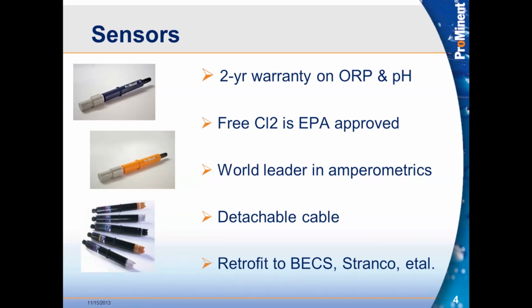Our free chlorine sensor is EPA approved, and it's the only chlorine sensor that has this approval rating to be used in drinking water applications without a backup wet test kit to verify the accuracy of results. To me, that's amazing. What that speaks about is the accuracy and performance reliability of the Prominent free chlorine sensor, as opposed to anybody else in the industry right now promoting free chlorine sensing for their controllers.